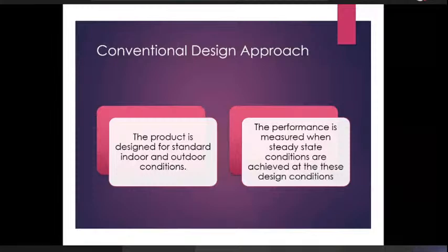If there is an energy labeling standard, for example, that energy labeling standard that we have in India, and just to divert the discussion a little bit differently, when I started working for Carrier in 2001, we had an opportunity to benchmark different products sold in the market. And since the 1.5 ton was the largest selling air conditioning product, we picked up units from the market and we tested them for performance. And what we find is that every manufacturer had a deviation from rated capacity. And the deviation was in most cases in excess of 10%.